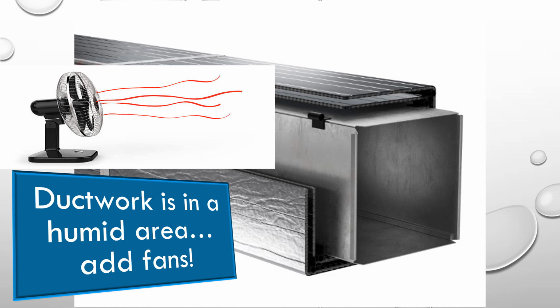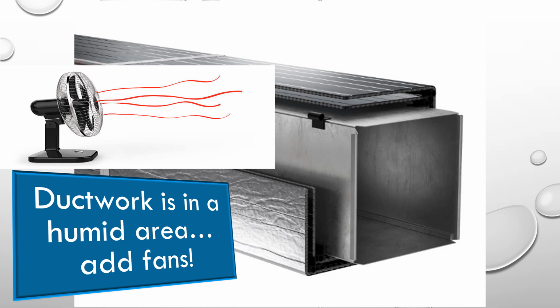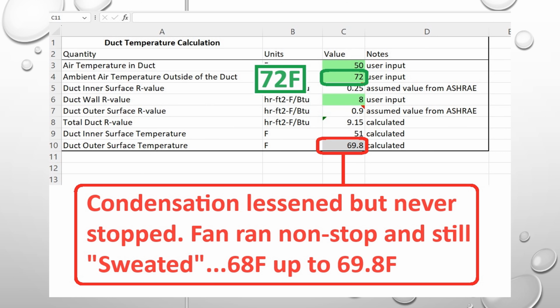All right, so on this slide here, we went ahead and added a fan to the crawl space, I guess hoping that you could take that 80 degree Fahrenheit air and add a little bit more heat to that crawl space to get the ambient temperature up, which we did get up, but it still was not enough. We found that the condensation lessened, but it never really fixed it.